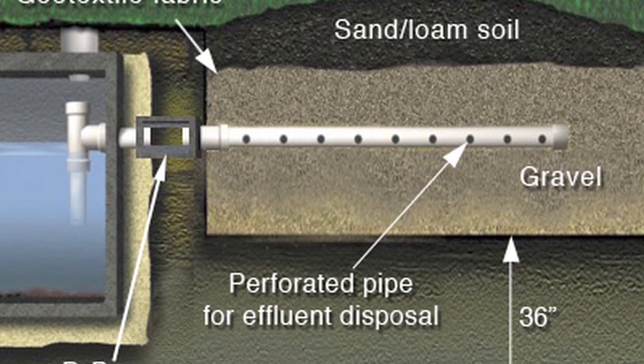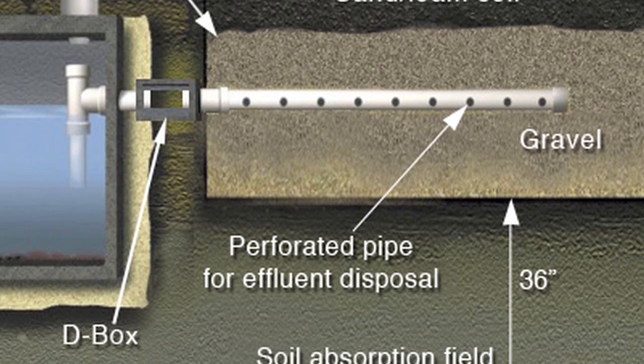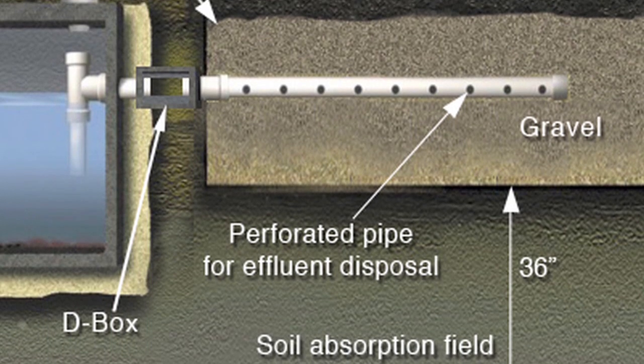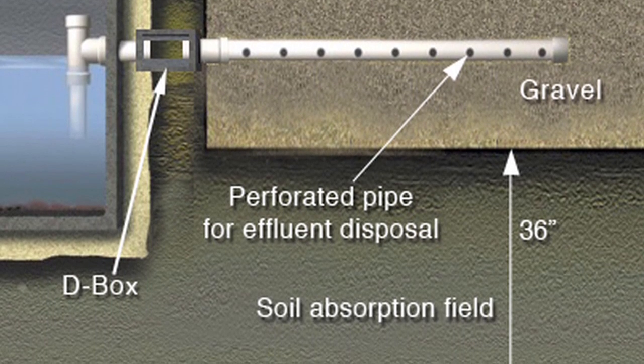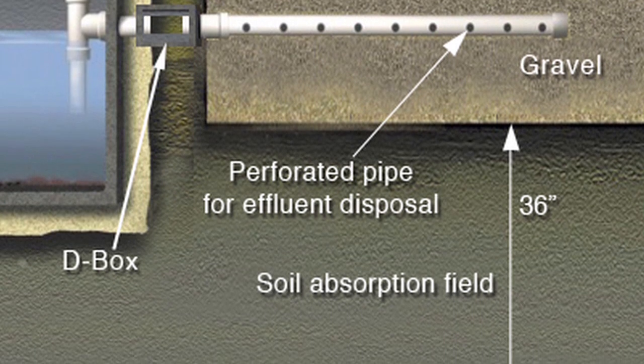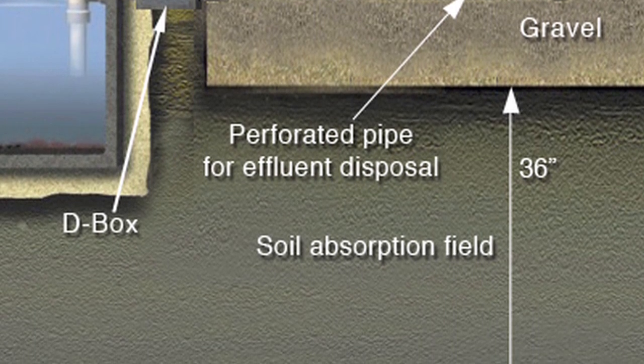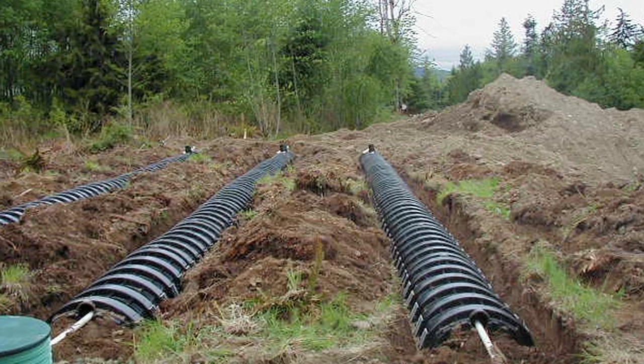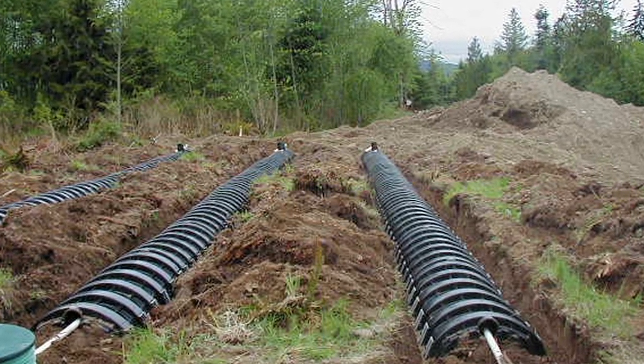This treatment is critical in protecting groundwater and surface water resources. Here we can see a cross-section of the drain field. The perforated drain pipe sits on a level grade with gravel. The gravel provides a space for the effluent to move. Above the gravel is a fabric layer to keep the upper level of fine soil from moving down into the gravel. Here's an example of gravel-less chambers used in place of rock and filter fabric.